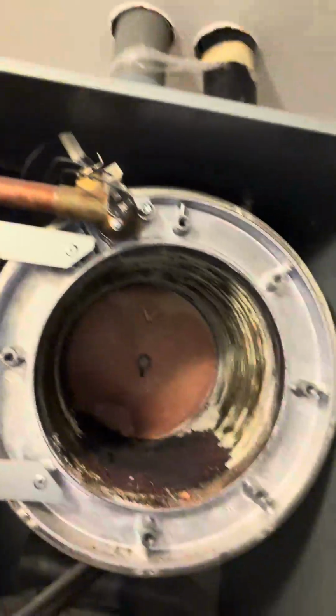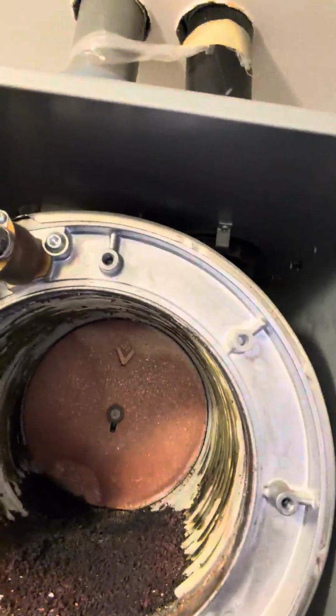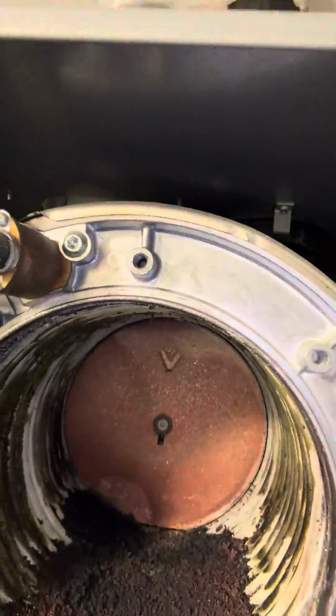I'm here in Vancouver. There is a problem, F4 error code on this Viessmann boiler, which is the most common problem. This is the heat exchanger, which is pretty dirty. I have to clean it up. And this is what the igniter looks like, and it's not really in a good condition. Most likely I would have to replace it.